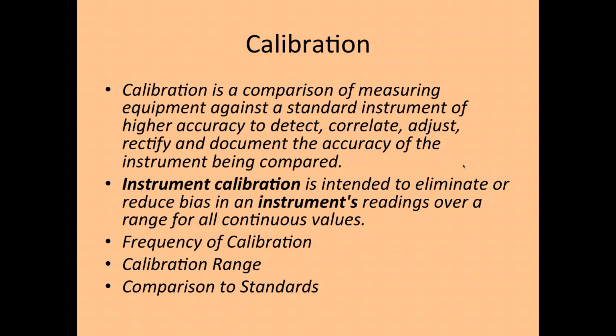I went a little deeper into calibration with this one. Instrument calibration is a comparison of the measuring equipment against a standard instrument of higher accuracy. So if you're looking at a scale, and the scale says that it's accurate plus or minus a thousandth of a gram, was it tested against a standard instrument? Is it tested to a NIST, National Institute of Standards, and is it at a higher accuracy so that you can document the accuracy of that equipment?